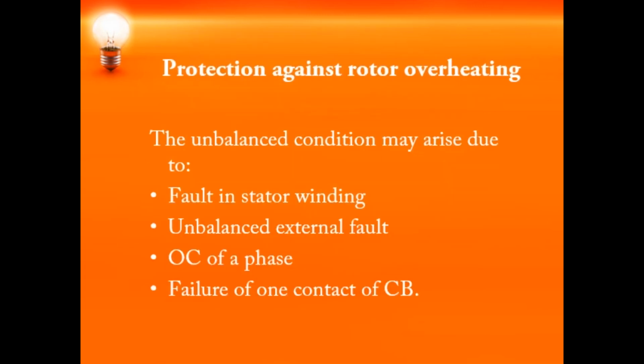So the negative sequence component of the unbalanced stator currents will cause a double frequency current to be induced in the rotor iron. So if this component is very high, then the overheating of the rotor will also be very high. The unbalance in the stator currents usually occurs due to a fault in the stator winding, or whenever there is an external fault that is not cleared quickly, or an open circuiting of a phase, or whenever there is a failure of one contact of the circuit breaker.